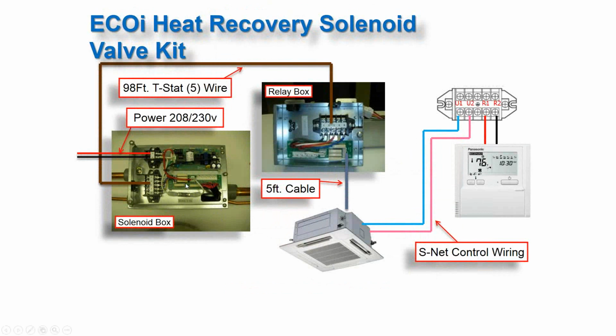Okay, and basically what this is doing is it's taking 3 pipes from the condensing unit, because our heat recovery systems are a 3-pipe system from the condensing unit. So we accept 3 pipes at this box, and this box converts those refrigerant pipes into two pipes, and that's where we would pipe to our indoor units from there. So this is the single zone look, but we have a 4, a 6, and an 8, so we can connect up to 8 indoor units back to one box. So this is part of the magic as to how we do simultaneous heating and cooling with one MF heat recovery system.